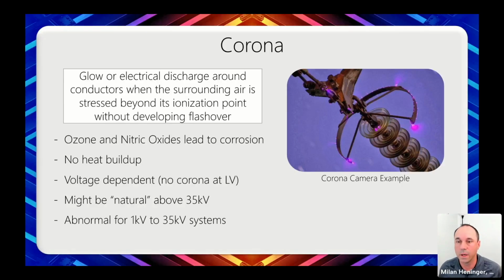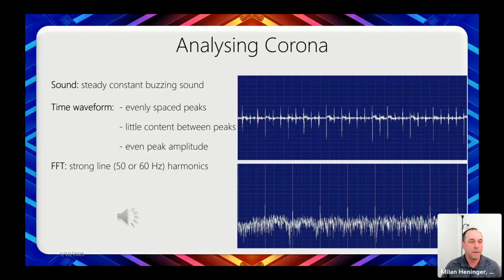So when we analyze corona, what we're usually hearing is a steady, constant buzzing sound. When we look at the time waveform, we'll see evenly spaced peaks with very little content. Sometimes your negative sequence is a little bit longer, but relatively even peak amplitudes. We do expect to see harmonics that are quite strong at the line frequency. So in the United States, this would be 60 hertz, but if you're abroad, it could be 50 hertz as well. So here's what it typically sounds like.